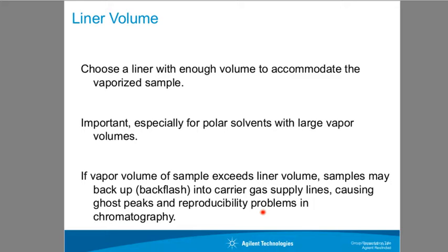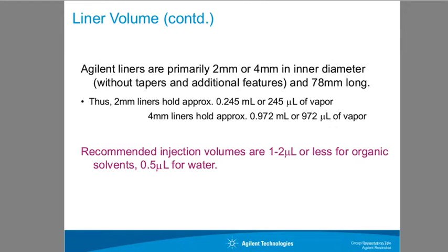It cools the inlet ever so slightly, so it creates a little bit of a vacuum and pulls things back in there. So typically, if you're seeing your analytes on blanks, it's because you have experienced some type of backflash at some point in time. And maybe we need to go in and address that, clean things up one way or the other, or just keep running blanks until you get rid of things.